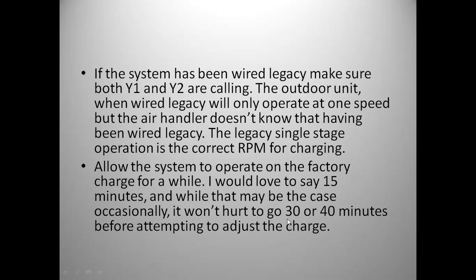I wouldn't make any adjustments to the charge until it's at least 30 or 40 minutes before you start. What can happen is if you start adjusting too early and that unit continues to run and stabilize, your pressures will continue to climb, and then you may end up actually overshooting your subcooling and overcharging the unit.